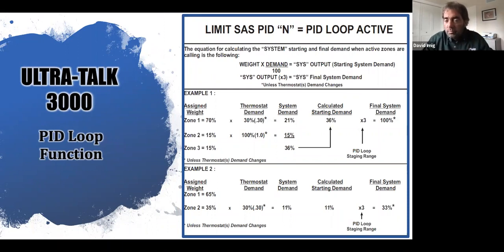And we're getting a demand of 30% from our thermostat. That means that we have a communicating thermostat in zone 1. Why? Because a communicating thermostat has the ability to give you the following demands: 30%, 60%, 75%, or 100%. What determines what kind of demand it gives you? That is based on how far away our actual temperature is in that particular area as to the setting on the thermostat or what it's trying to achieve.